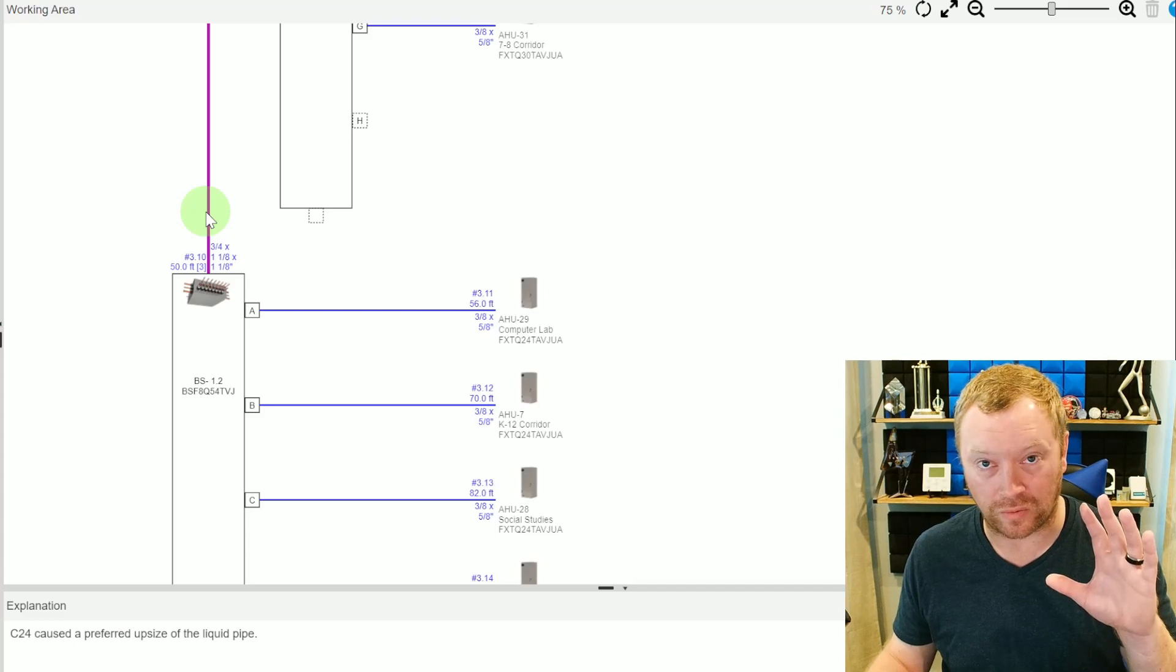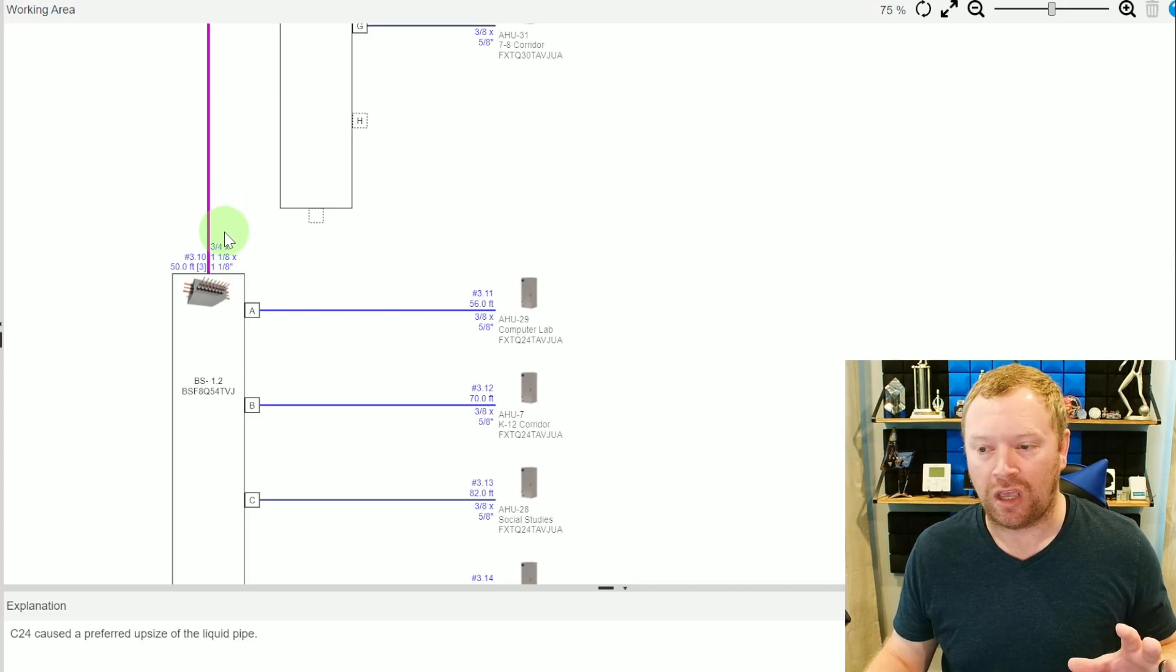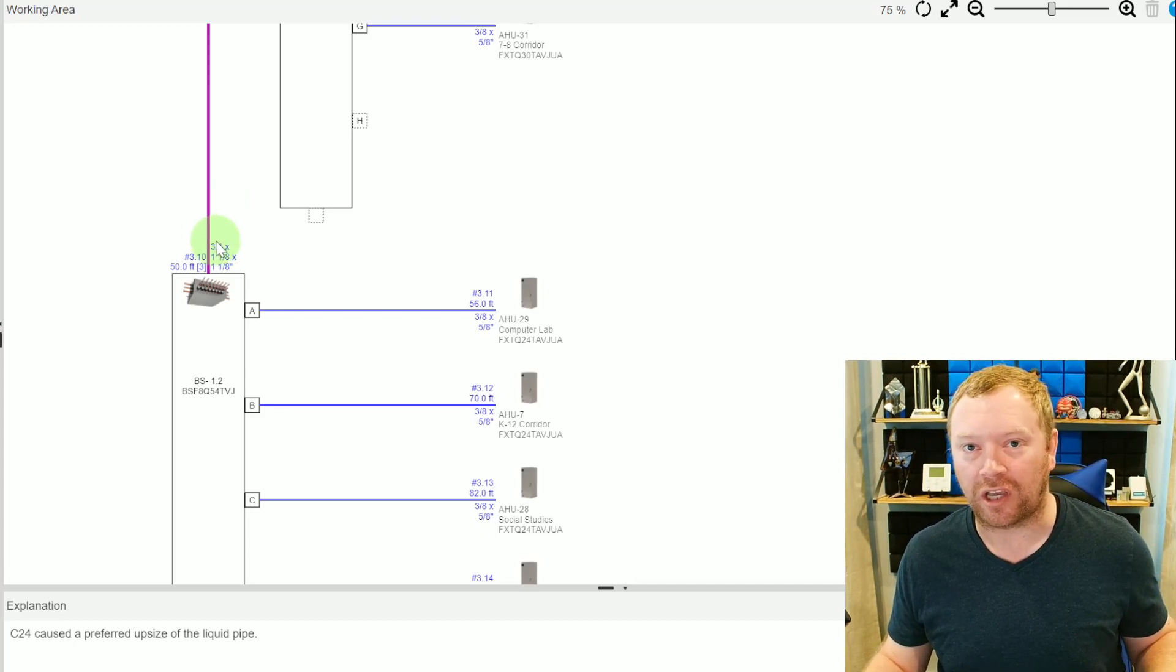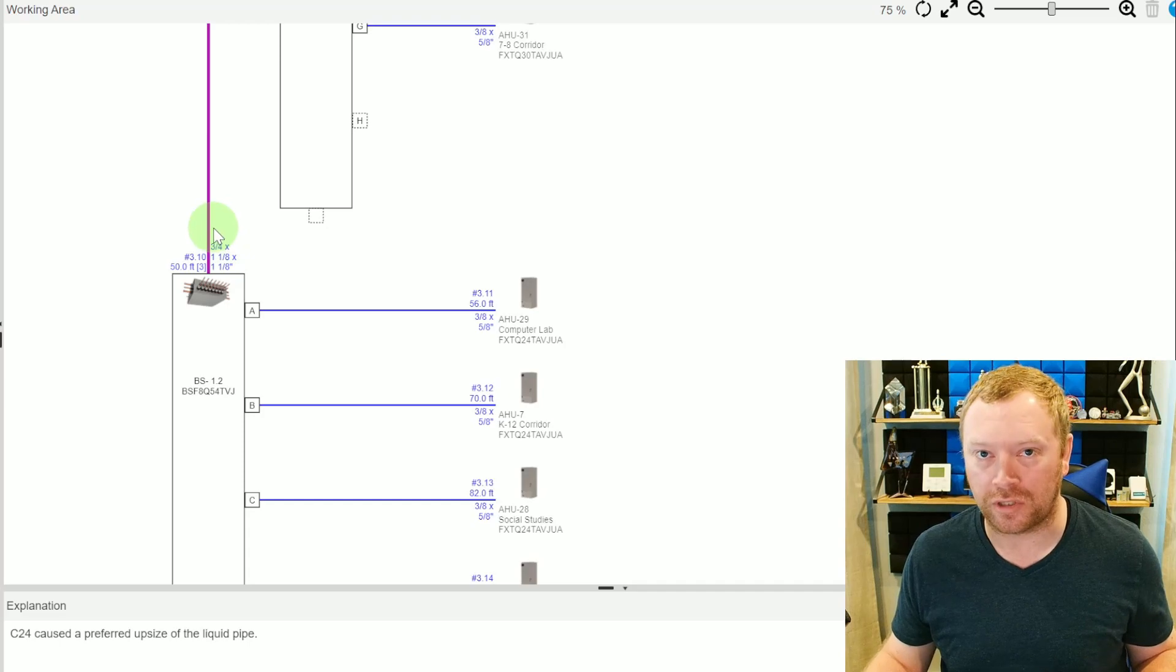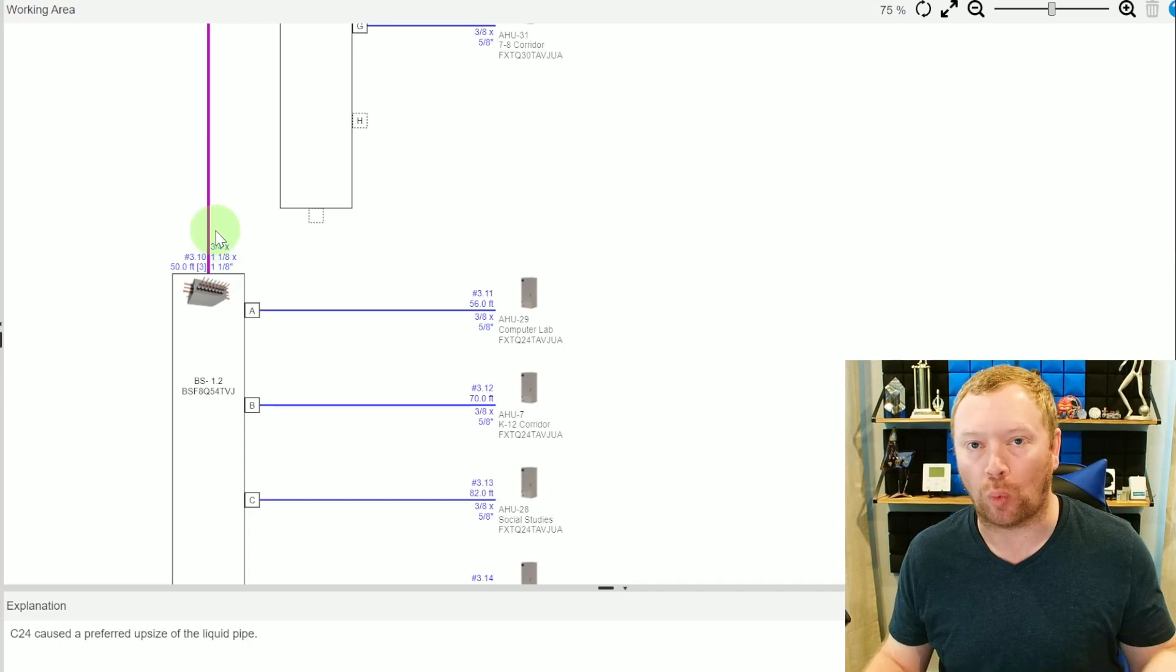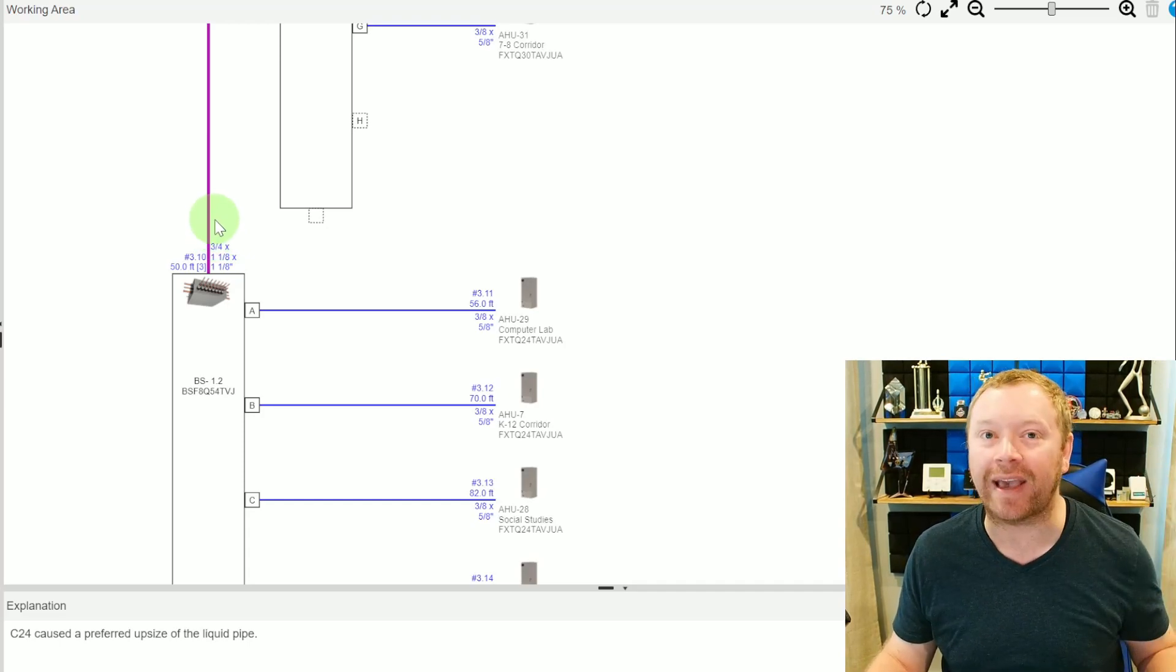This is where I really get frustrated is all of a sudden we want to try to come up with new numbers to try to make what we installed work. You guys can't do that. It is very, very frustrating. If you guys are off, you guys are off. Okay. And you guys as installers need to know that if you don't have the right size pipe, the right length measured, your charge is going to be inaccurate and the charge calculation itself will be wrong because it's doing the charge calculation based on a certain size liquid line. So now you're potentially overcharging or undercharging the system just because of that alone, not to mention your lengths may or may not be accurate. And the system is going to have performance problems at some point, maybe not today, maybe not during the startup, but at some point you're going to have performance problems and you could potentially have oil return problems. And if you don't get oil back to the compressor, you're going to lose a compressor.